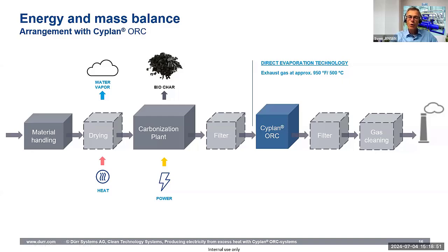I mentioned that normally it might be higher than that. So what we do is recirculate the flue gas, which we have cooled down to around 200 degrees Celsius, back to the front and mix it with the hotter gas, achieving the desired temperature of about 500 degrees Celsius.